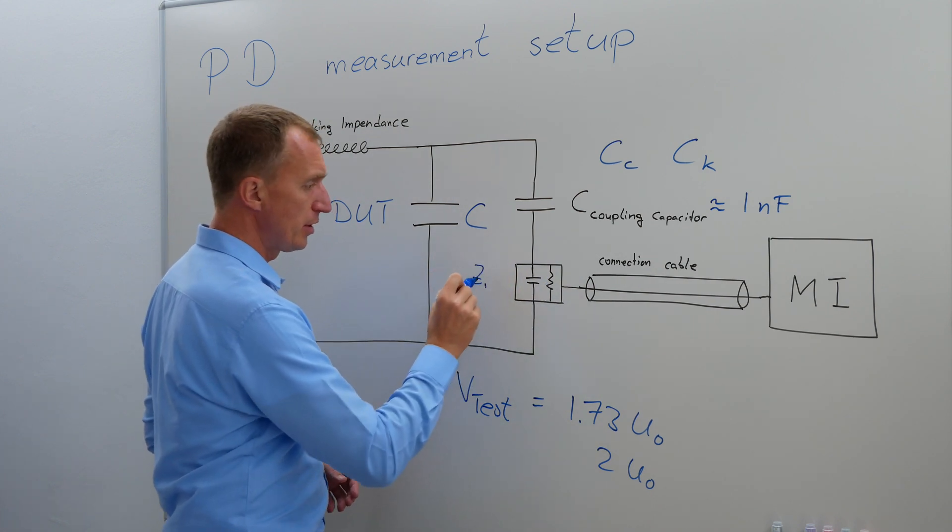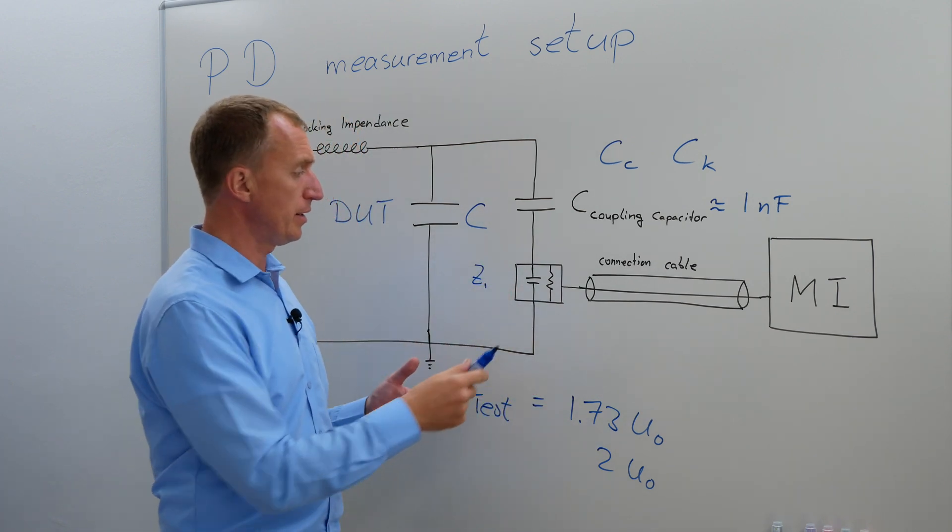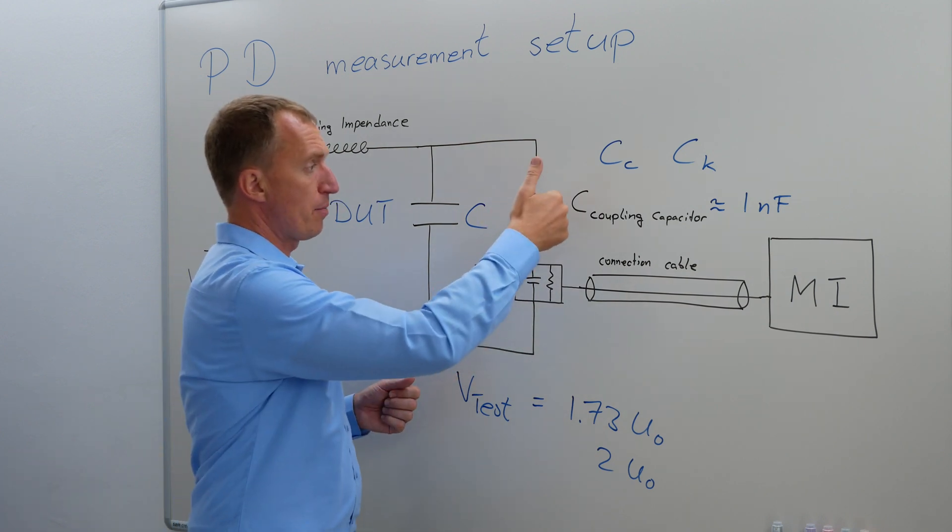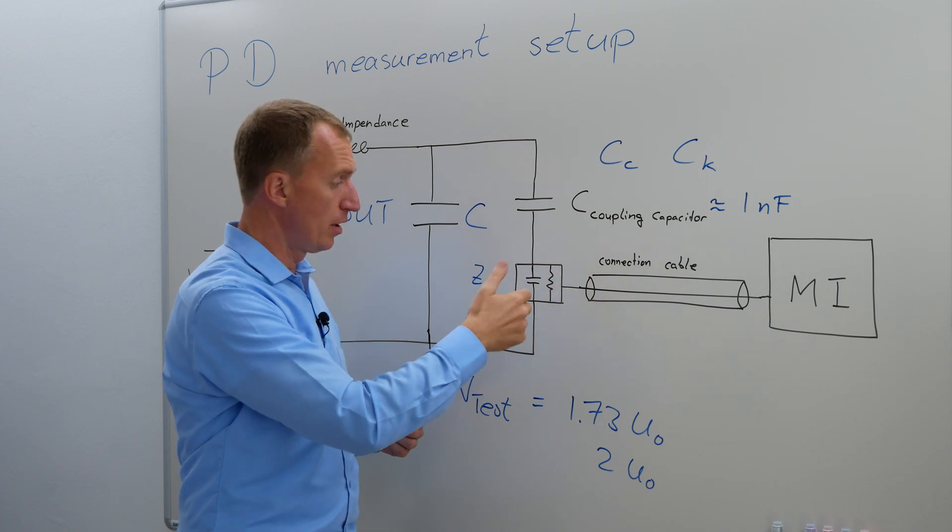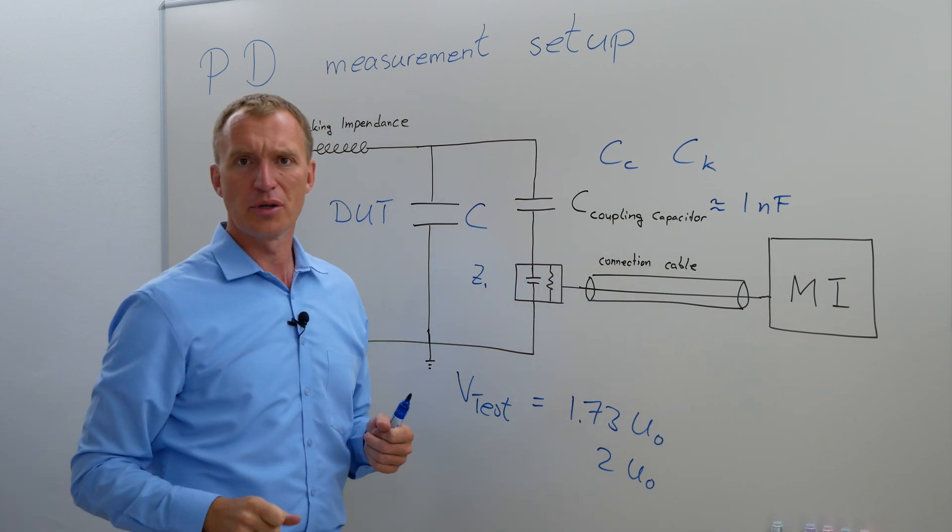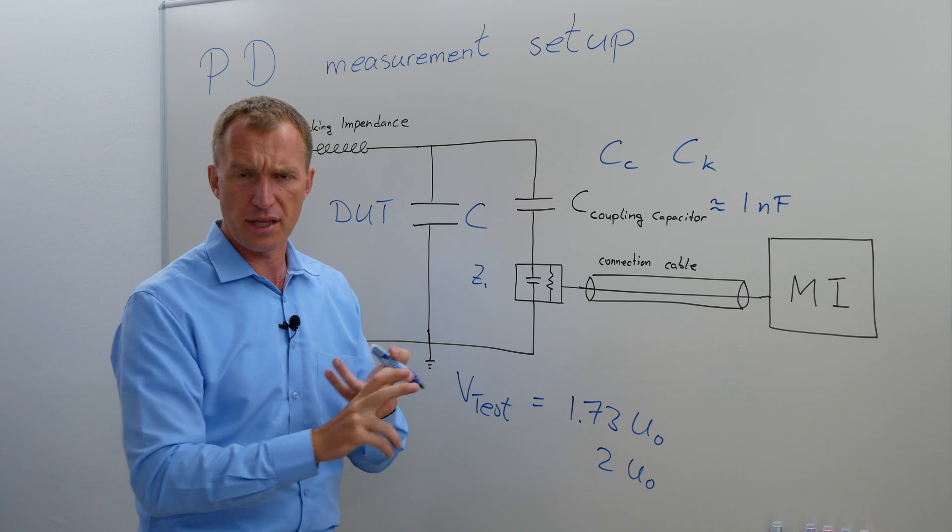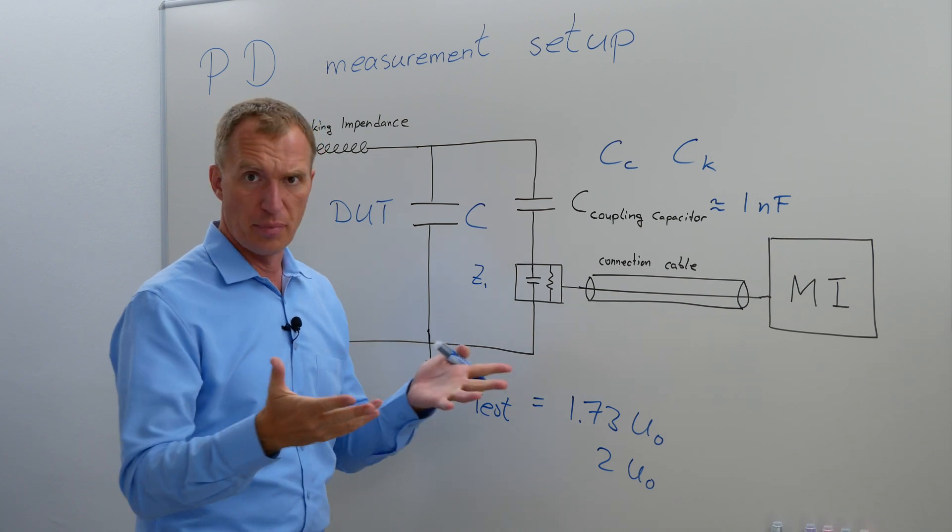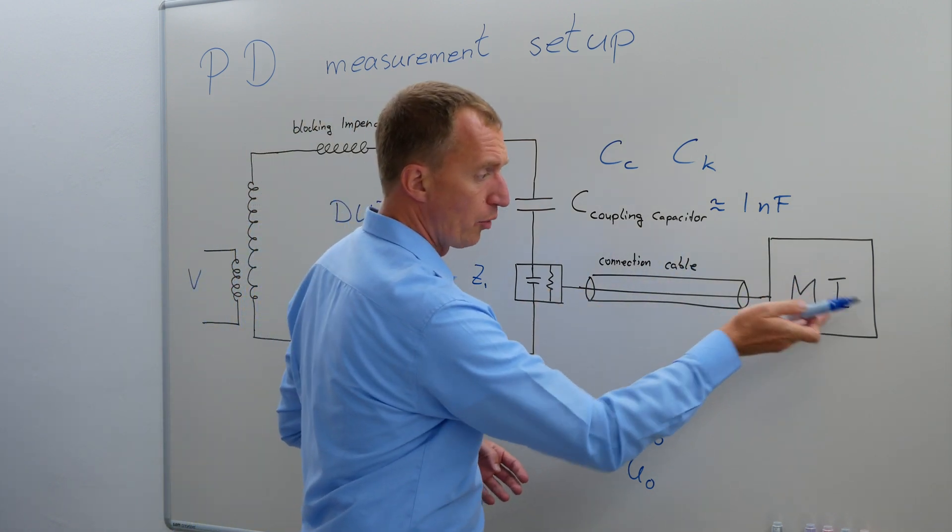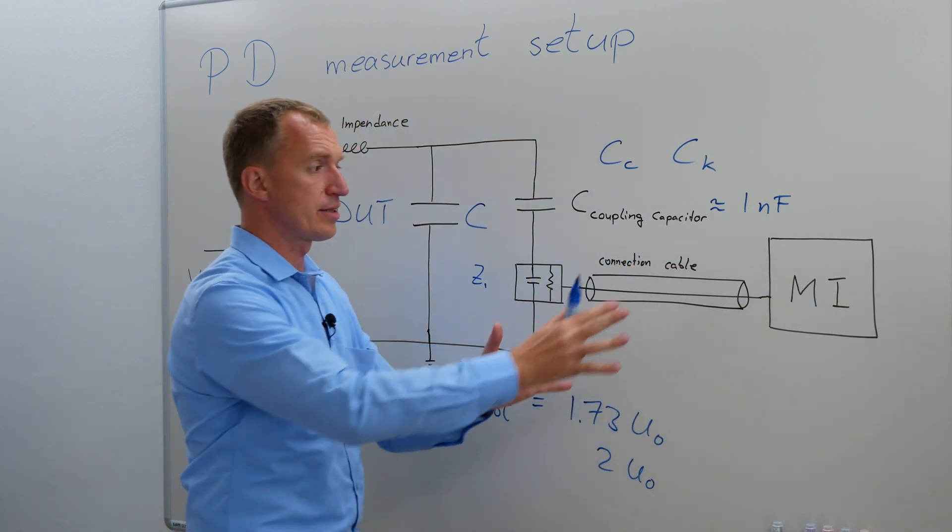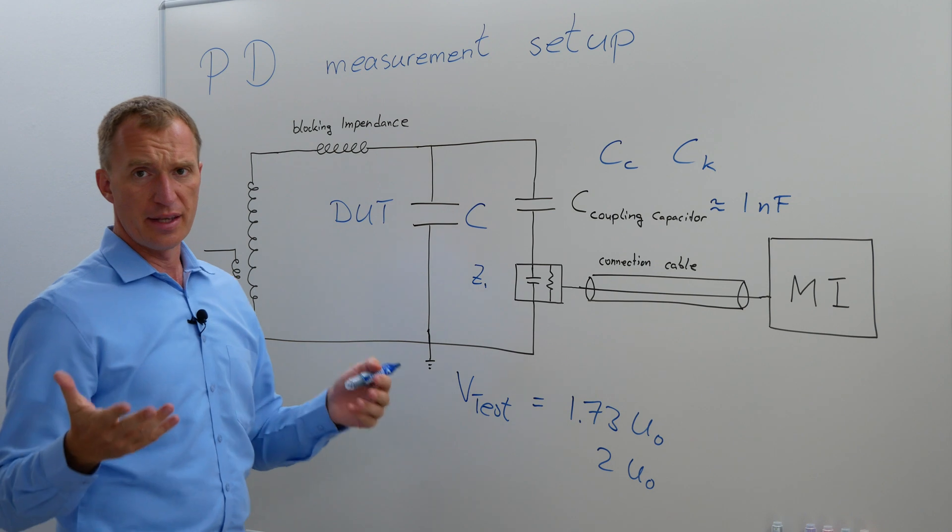Now here you have a measuring impedance. Some companies call it a quadripole. This quadripole is technically a capacitance as well, and it creates the capacitive divider between the high-voltage coupling capacitor and this low-voltage capacitor. I drew a small resistor in here because we're getting two signals: the charge signal, the partial discharge, and furthermore, the voltage information. We have a connection cable to our measuring instrument. These things are kept rather easy and simple. So that's pretty much it.